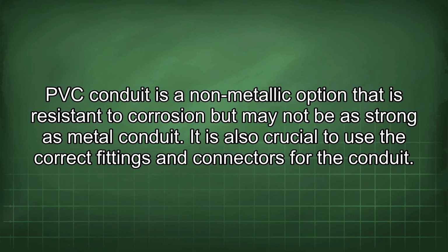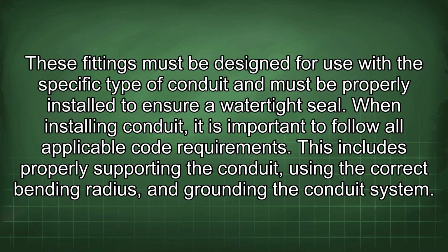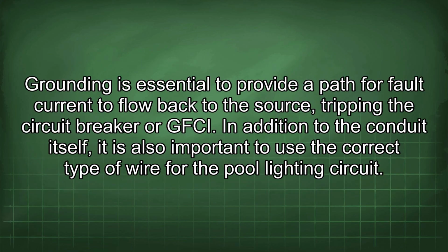It is also crucial to use the correct fittings and connectors for the conduit. These fittings must be designed for use with the specific type of conduit and must be properly installed to ensure a watertight seal. When installing conduit, it is important to follow all applicable code requirements. This includes properly supporting the conduit, using the correct bending radius, and grounding the conduit system.